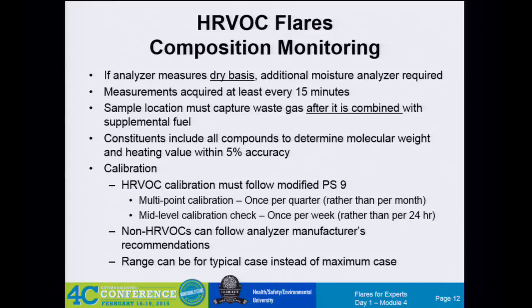So the rules don't allow you to measure vent gas and the supplemental gas flow and then calculate? That's what you would have to do. But the composition analysis must be when they're together. Okay, so you have to measure it. Yeah, so that's where that flow meter on the supplemental fuel line becomes critical. Otherwise, you could just be pumping a bunch of fuel in there and saying, well, look, my number's great, but you're wasting a lot of extra gas. So from a minimization standpoint, you're going to want a little more robust monitoring on this system.